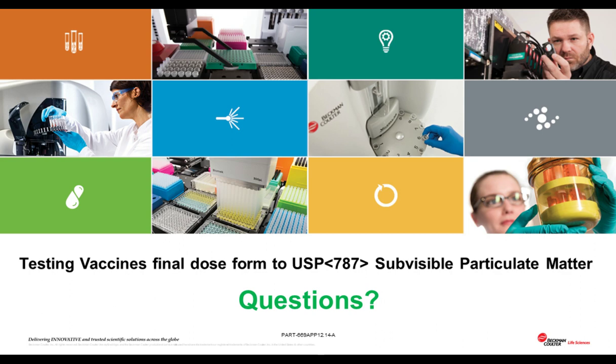And this means that we can count irregular shaped contaminating particles and size them according to certified reference standards, which gives us the traceability. And no matter what their shape, the particles that obscure the same amount of light will be reported as having the same equivalent spherical diameter. And of course, the main impact here is it helps to reduce the impact of subjectivity and human error on these measurements.